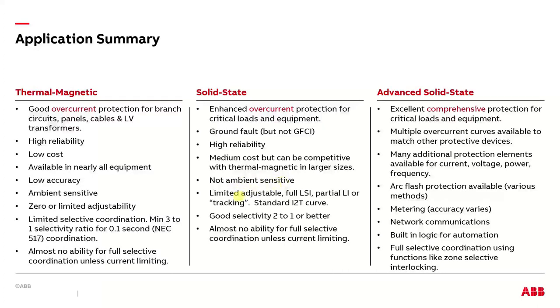Insensitive to ambient changes in temperature, adjustable, better selectivity than you would get in the thermomagnetics. You can do a 2-to-1 ratio, which is comparable to fuses. So you could coordinate a 50 amp breaker with a 100 amp breaker solid state without an issue. And you could probably do better, up to like a 1.5 to 1. Full selective coordination is still an issue.